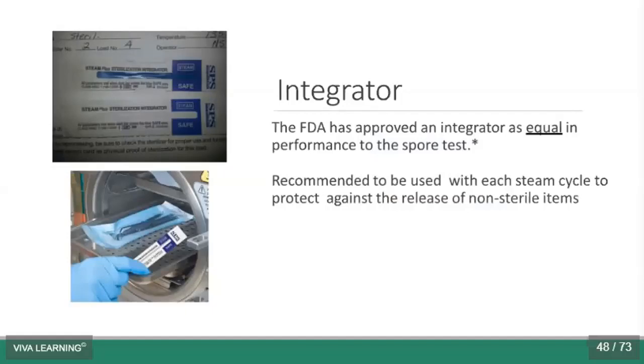So what is an integrator? An integrator is also a type of chemical indicator. It's the highest level of chemical indicator, as a matter of fact. And here's where the FDA comes in again. The FDA has approved an integrator as being equal in performance to a spore strip test. Now, it's very important for me to share with you, this does not mean it replaces the requirement for you to use a spore strip test.